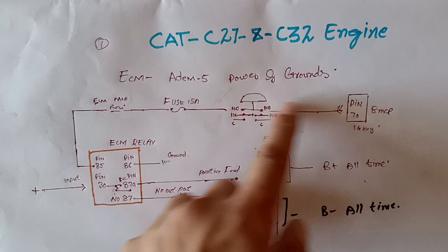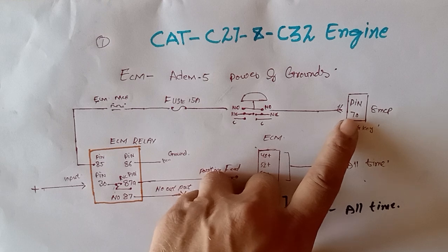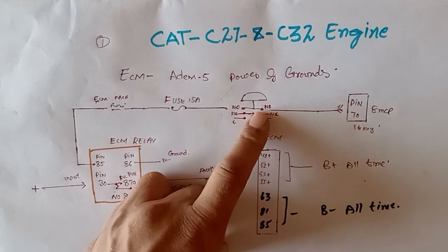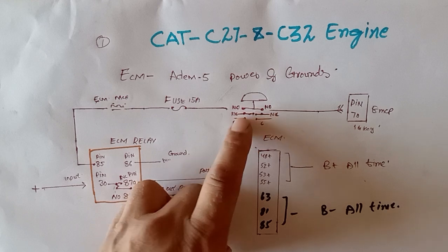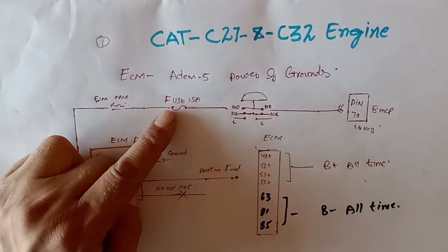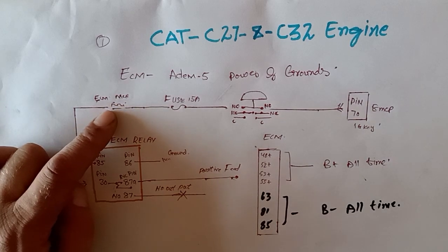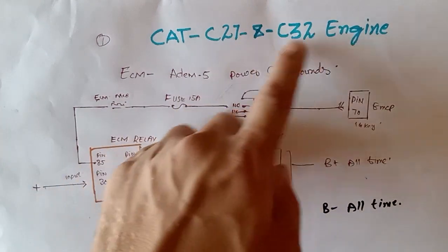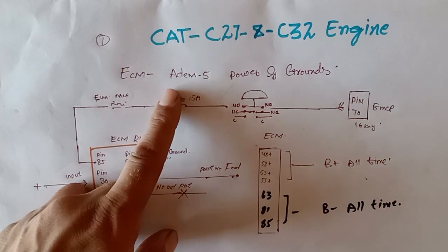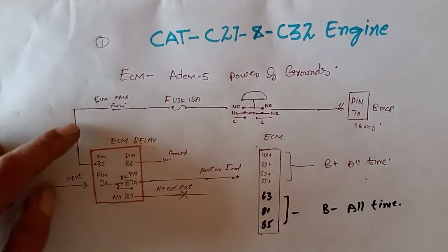From the EMCP 70-pin connector, pin 70 is the output for the ignition key switch. It goes into the emergency push button at the NO (normally open) contact, then out from the NO contact and into a 15-ampere fuse. From the fuse, it goes out to the ECM miniature circuit breaker. These two types of engines have circuit breakers for the starter motor, fuel solenoid, fuel activator, ignition system, and the ECM relay.